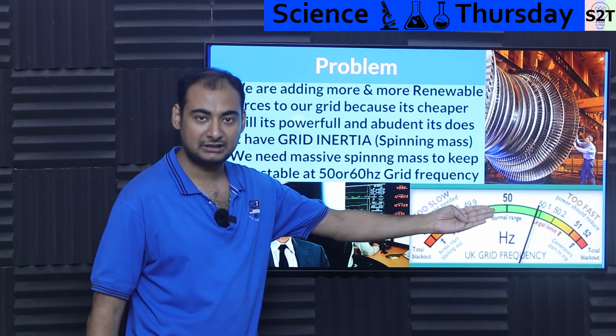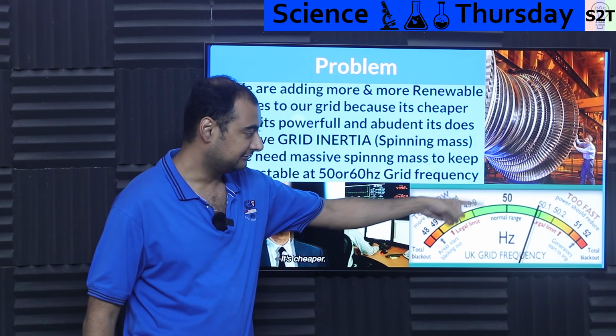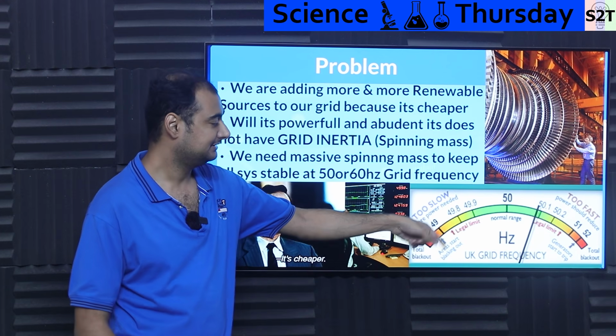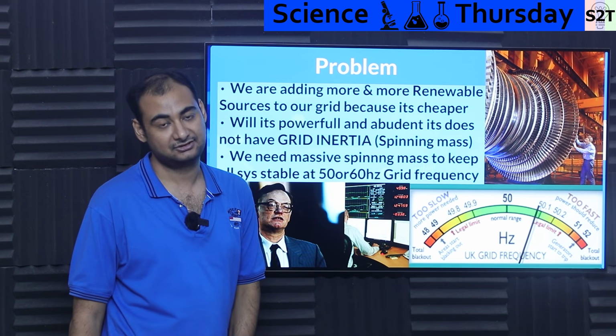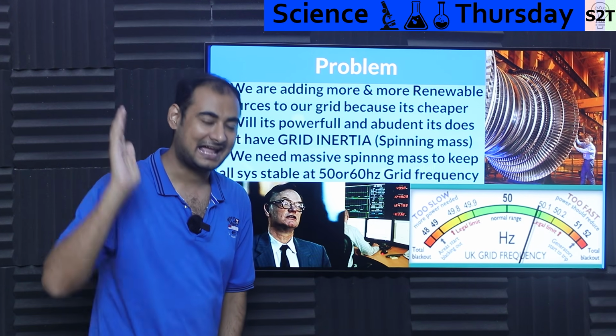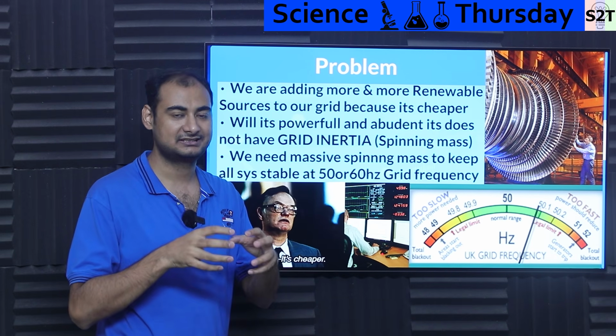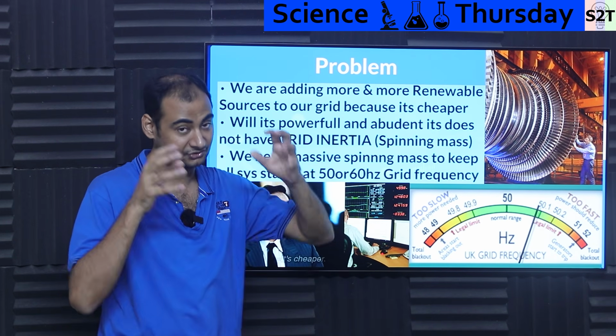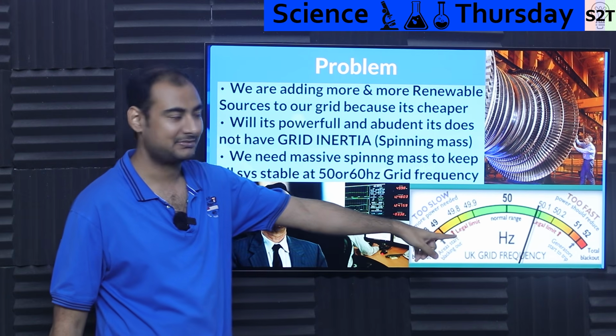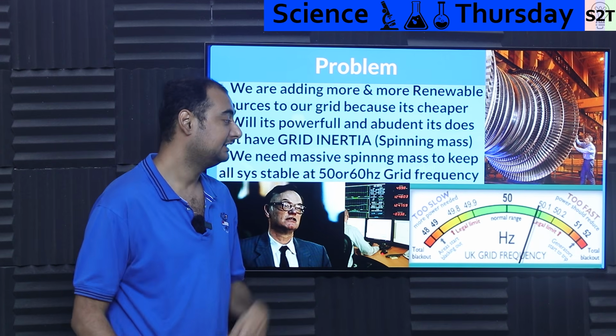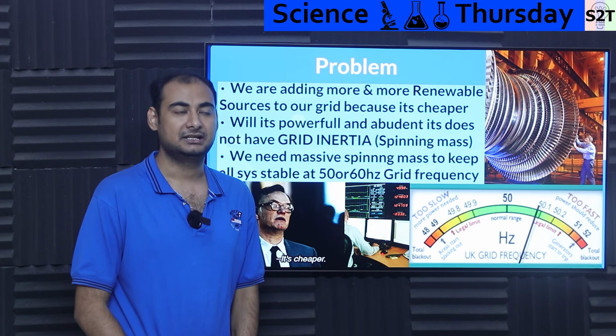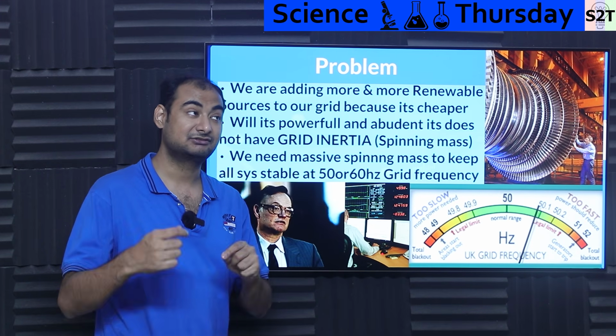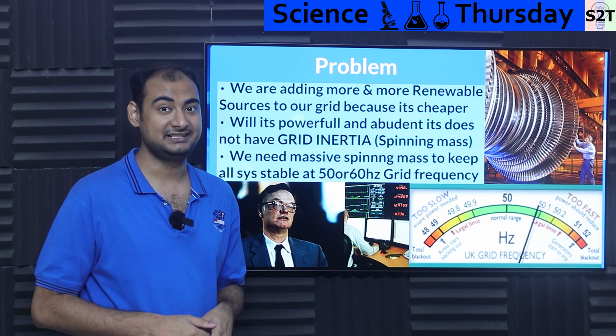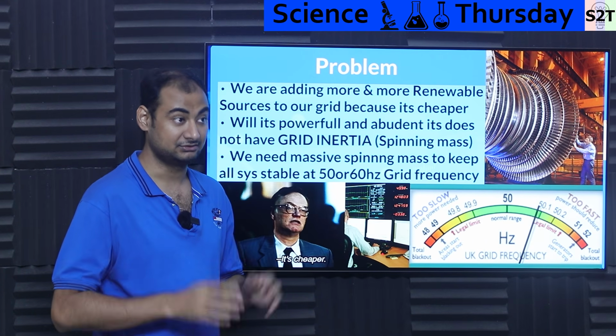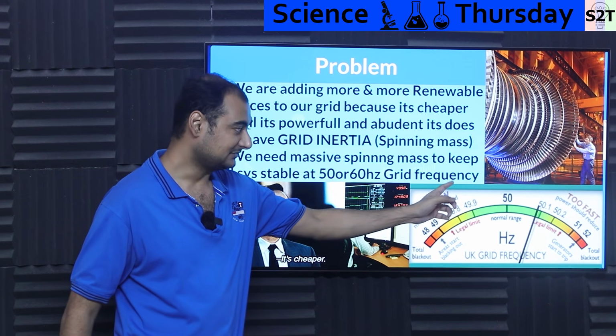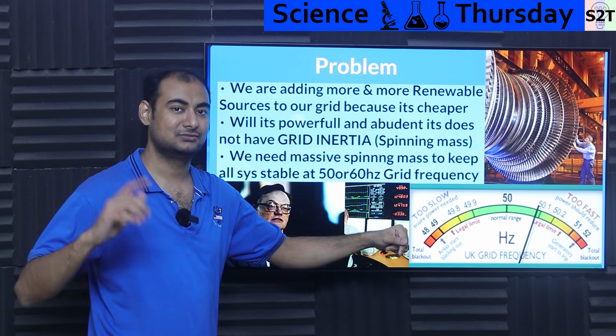And then if you keep going higher, let's just say you're still overproducing and it crosses 51, this is red alert. The moment you start to touch 52, generators will start to trip, because that's the last line of defense. The generator has to cut power. The generator itself has a circuit breaker, not the substation circuit breaker, and those are generally set to trip at 52. And what happens if it goes even further than that? Yeah, total blackout. What does total blackout mean? The grid has lost inertia, meaning you have to start all of them one by one. It could take days. That's not something like a circuit breaker, so no, you have to start a power plant. That happens when you have too little energy draw and too much production.